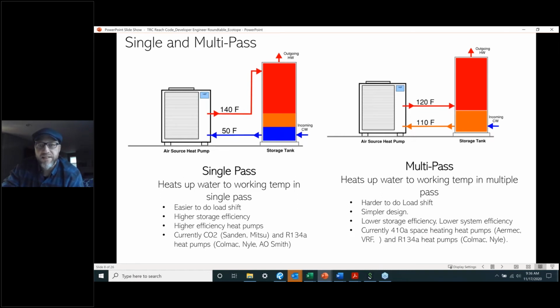The other way is the multi-pass, and multi-pass is very similar to a gas boiler. We're heating the water up in 10-degree slices, so every time it goes through the heat pump, we add another 10 degrees until we get to set point. If you run the recirc through that tank, which is very typical of multi-pass, your heat pumps will run all the time. We're trying to set these up as thermal batteries, and this is the reason you want to decouple the circ loads from the primary storage. We want to have this reserve of really hot water so we can float through the high peak rates.